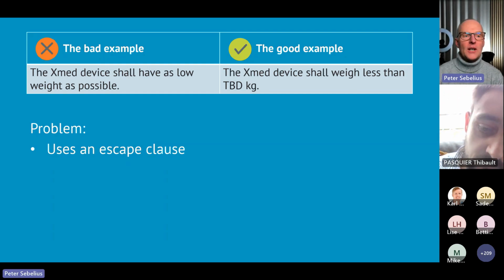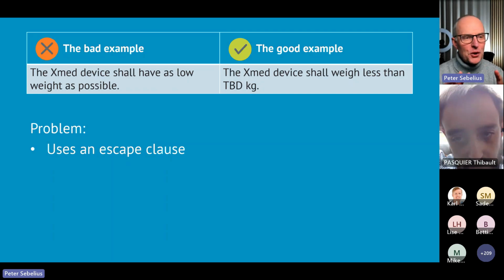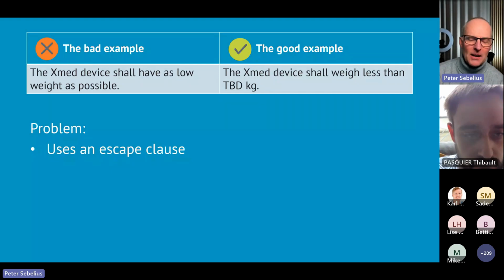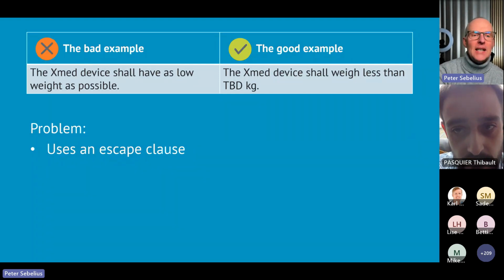So generally speaking, I would say that the things I've shown you now, the problems with these requirements, would notified body auditors pick up on that? Well, quite rarely. But here, I would say that there is a significant risk that you would have a non-conformity if you write a requirement with this kind of escape clause, because the auditor might pick up on the lack of clear acceptance criteria and say, well, we don't know when this is acceptable or not, which is a good point. So this you should definitely avoid if you want to avoid non-conformities.